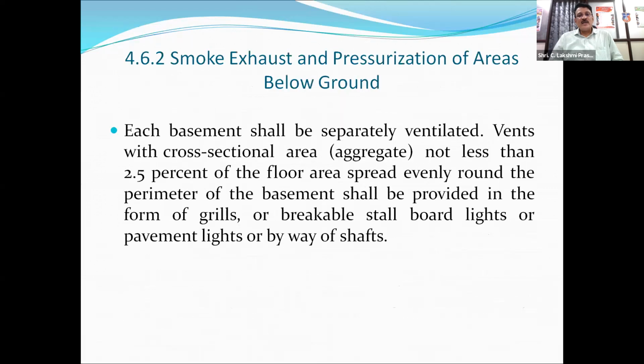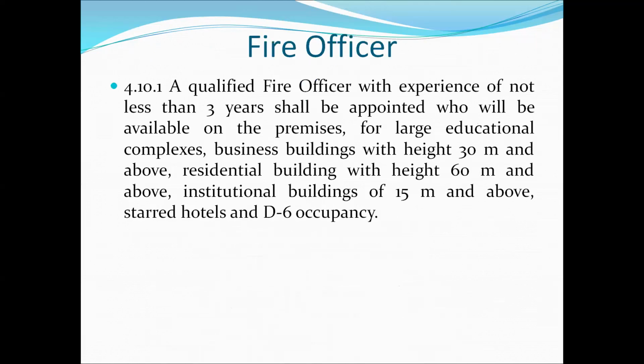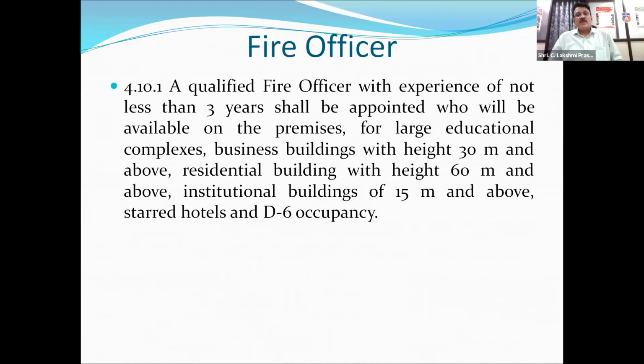Then smoke management is again one specialization. It comes under the purview of the HVAC engineers, pressurization and smoke management. They are very, very vital in ensuring the life safety of the occupants. Then fire officer: for business buildings above 30 meters, residential buildings above 60 meters, hospital buildings of 15 meters and above, and star hotels, there should be a qualified fire officer to take care of the trainings, to ensure the systems maintenance and to ensure the life safety.